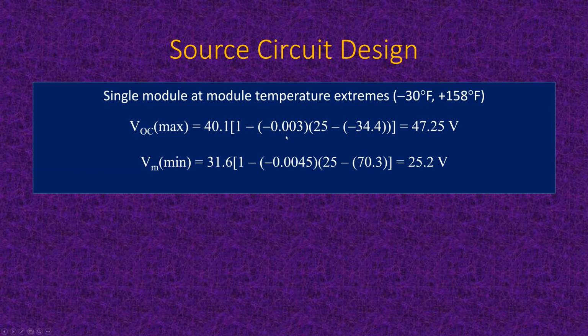It gives the 0.003 is the temperature coefficient of the open circuit voltage of the modules. And I guess this is assuming generally the folks who are taking a battery backup design course have had some experience with straight grid connect or with PV one way or another. So this is your temperature coefficient for the open circuit voltage. And you'll notice that it starts out at 40.1, but when it goes down to minus 30 degrees Fahrenheit, which is minus 34.4 Celsius, the voltage goes up from 40.1 to 47.25.